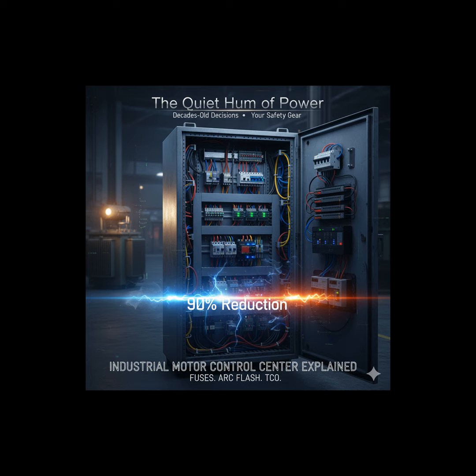Can you put that into relatable terms for the listener? What does a 90% reduction actually mean for the person working on that MCC? It means the difference between mandatory safety gear categories. A fast-acting fuse often clears the fault so rapidly that it suppresses the energy below 1.2 calories per square centimeter. At that level, standard arc-rated clothing is often sufficient. However, if a standard breaker clears the fault more slowly, the energy release can jump dramatically, potentially requiring a full Category 4 suit and gear rated up to 40 calories per square centimeter. That millisecond difference dictates the required PPE for every maintenance task for the life of that equipment.